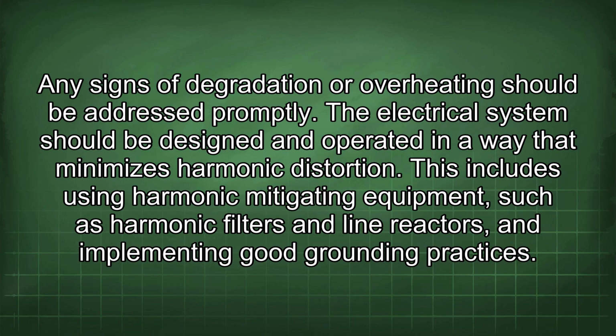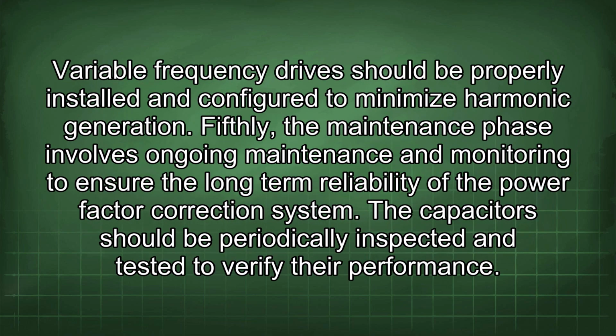The electrical system should be designed and operated in a way that minimizes harmonic distortion. This includes using harmonic mitigating equipment such as harmonic filters and line reactors, and implementing good grounding practices. Variable frequency drives should be properly installed and configured to minimize harmonic generation.